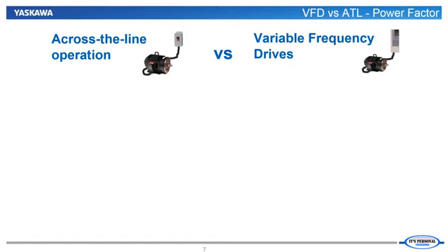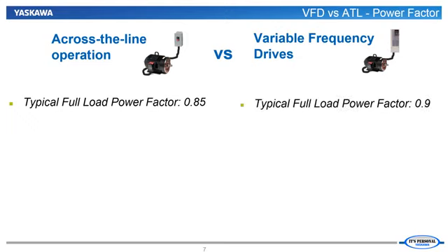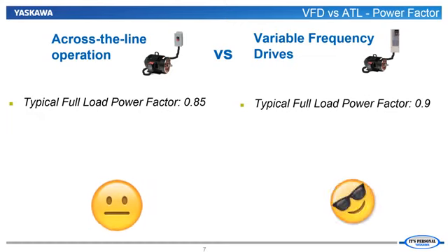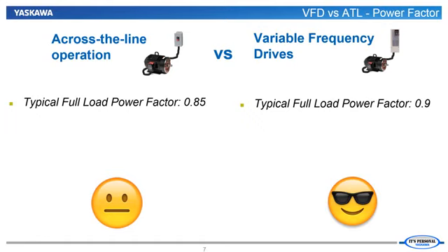Anyway, let's put some numbers to this power factor discussion. First, let's consider a fully loaded variable torque application, like a fan or a pump, running near full speed. When a motor is running across the line, the power factor is reasonable, but the inductive nature of the motor does tend to lower the power factor. When we take the same fully loaded application and drive it with a VFD, the VFD corrects for the motor's effect on the power factor.